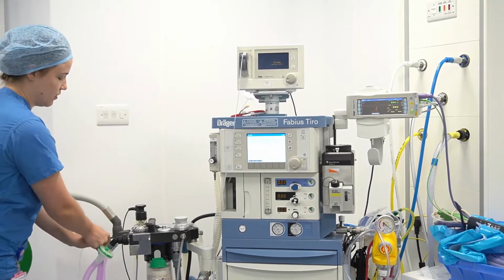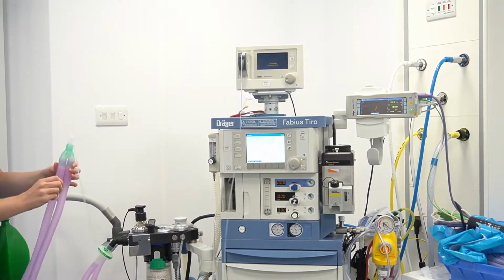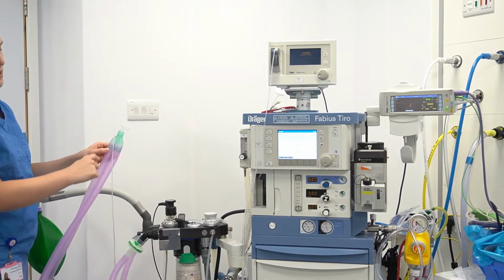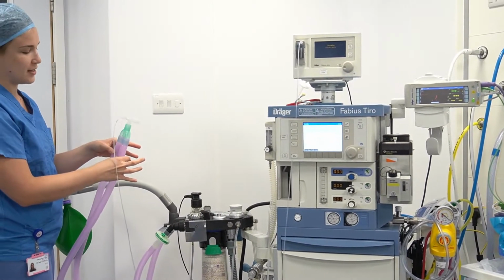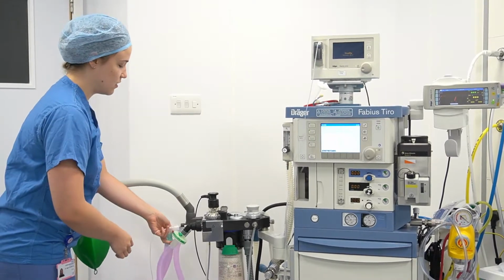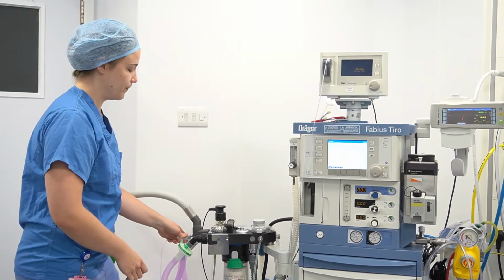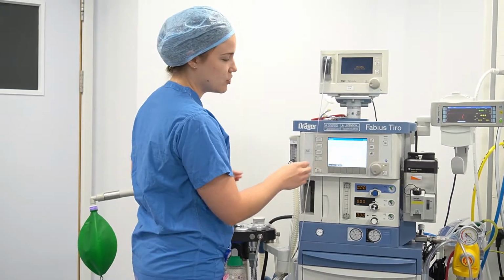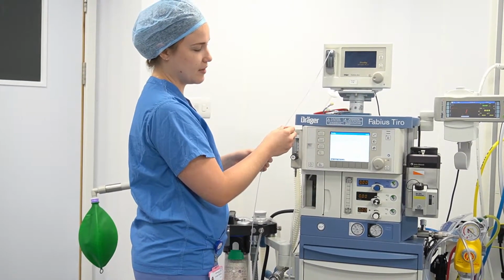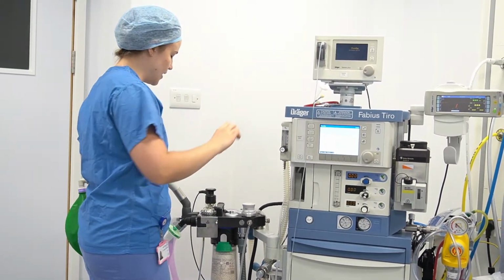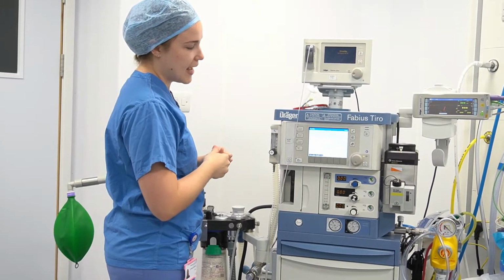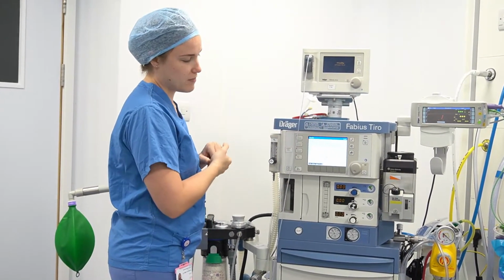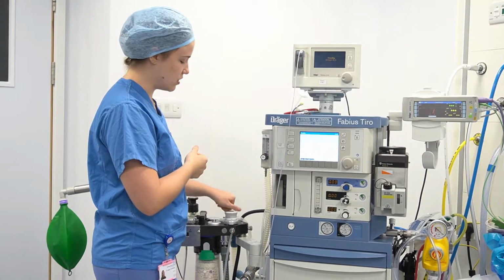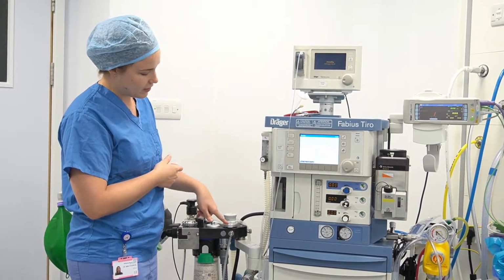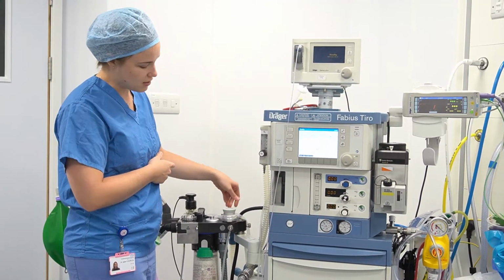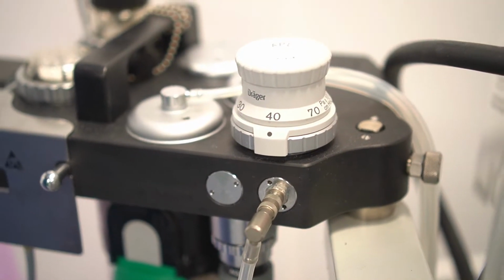So the Y piece is referring, sorry, that was already connected. So the Y piece is referring to this. It makes a Y as it's connected to your expiratory and inspiratory limb. Make sure that that is connected over there. And then make sure that the sample line connector is connected on both sides, and there's no leak over there. The next thing is to switch your APL valve to man and set it to a pressure of 40 to 50. So our APL valve is on about 20, and then just turning it to just over 40.